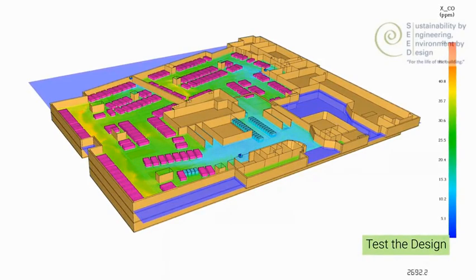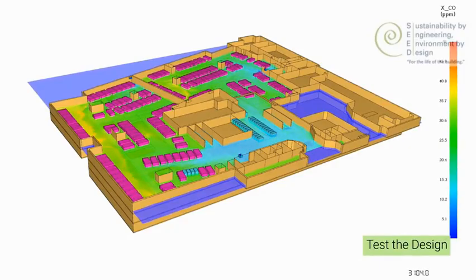We always test with the worst case hour to satisfy authorities. Another thing you need to test are the assumptions. Where the design relies upon natural ventilation, we need to test the different wind directions and ensure that under all conditions we're achieving a very good outcome. In this screen, basically the entire basement car park has got the same air quality as outside air.